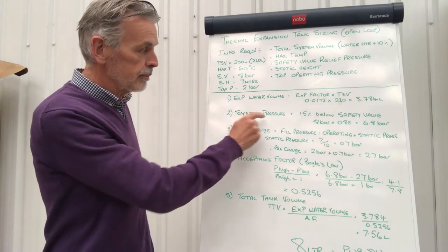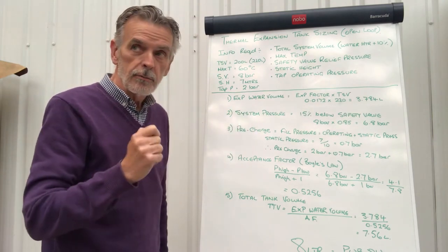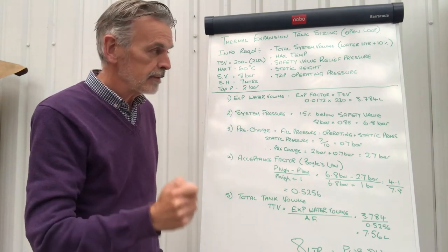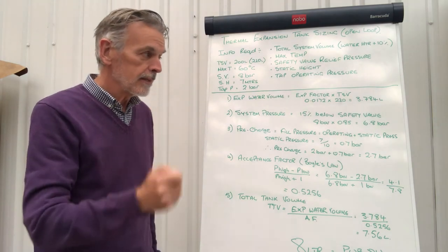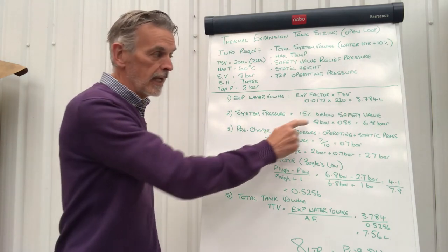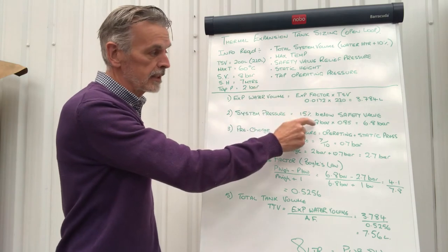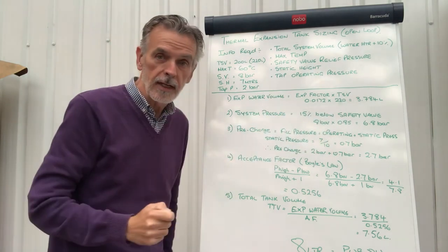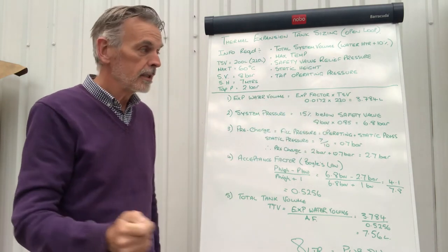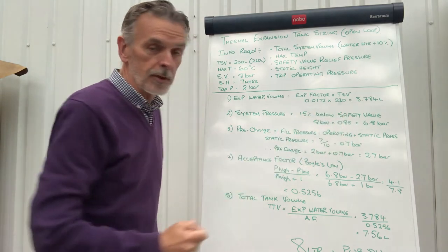Second point, system pressure. The system pressure we say should be 15% below the safety valve. So 8 bar, which is the 8 bar safety valve, times 0.85 will give you 15% below the 8 bar, which is 6.8 bar.